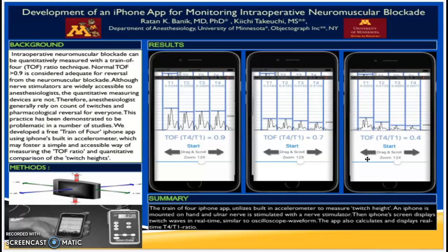He was very skeptical initially. Measuring train of 4 ratio with an iPhone, he didn't think it was a cool idea. But then he took me to the OR, and we tested this app on a few patients, and we were convinced that this app's output is almost similar to the commercially available train of 4 device.